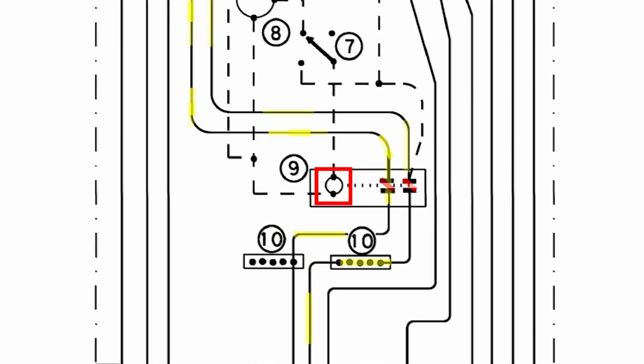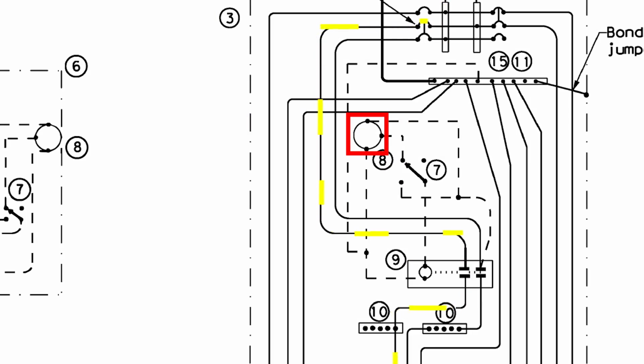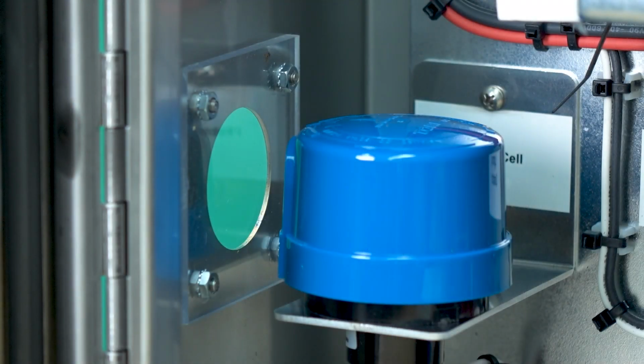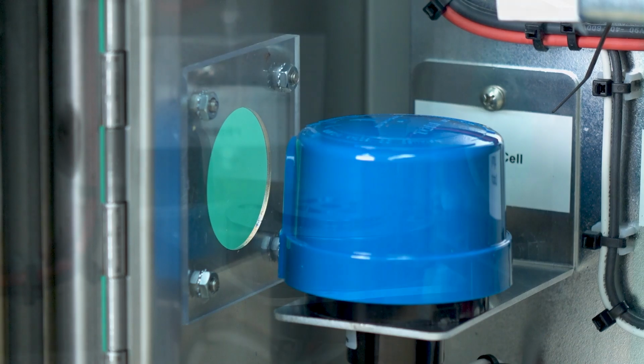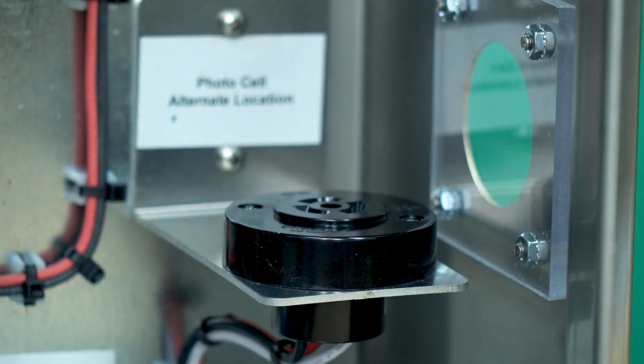The lighting contactor opens and closes the electrical path of the circuit. The photocell controls the power to the lighting contactor's electromagnetic coil. The photocell is controlled by the HOA 3-position selector switch. When the photocell is placed inside the Type D electrical enclosure, one of 2 small, clear viewing windows allows sunlight to be sensed by the photocell. The lighting branch circuit breaker controlling the power to the light fixtures is powered by the load center's bus bars. Conductors run from the load side of the branch circuit breaker to the line side of the lighting contactor.